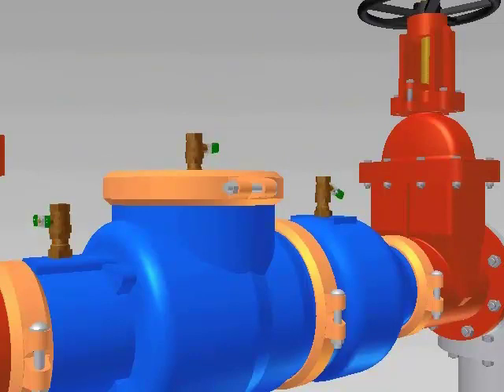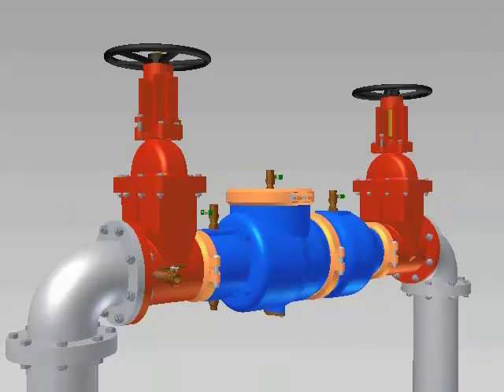Close test cocks. Open your inlet valve slowly to pressurize the assembly. Inspect for any leaks. Open and then close test cocks to bleed air from the assembly.